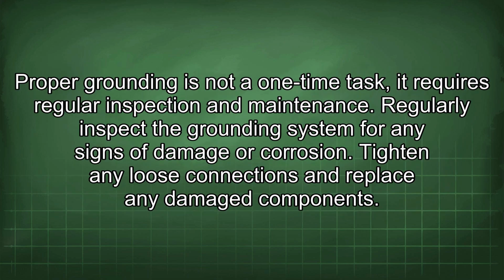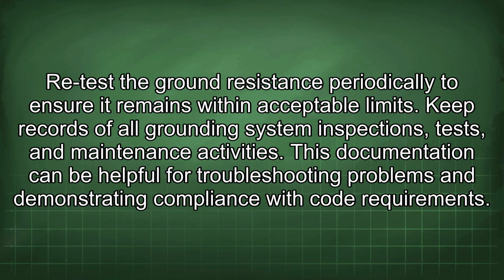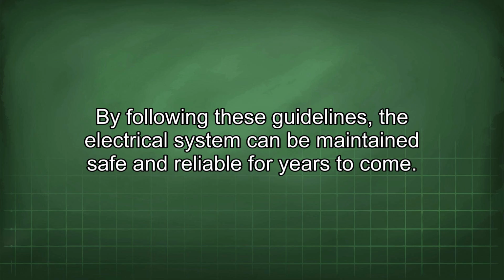Proper grounding is not a one-time task, it requires regular inspection and maintenance. Regularly inspect the grounding system for any signs of damage or corrosion. Tighten any loose connections and replace any damaged components. Retest the ground resistance periodically to ensure it remains within acceptable limits. Keep records of all grounding system inspections, tests, and maintenance activities. This documentation can be helpful for troubleshooting problems and demonstrating compliance with code requirements. By following these guidelines, the electrical system can be maintained safe and reliable for years to come.